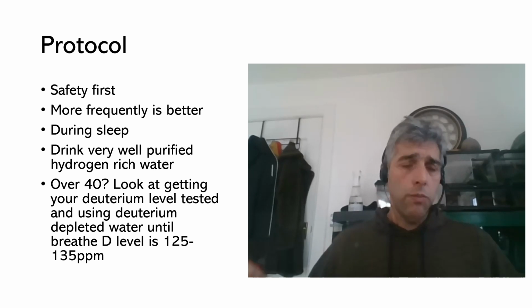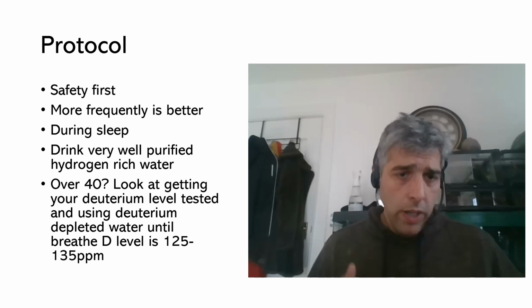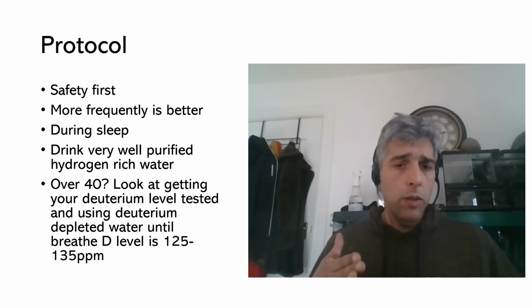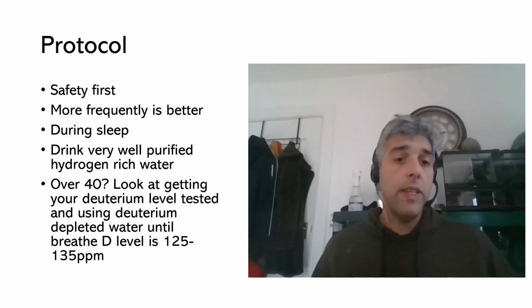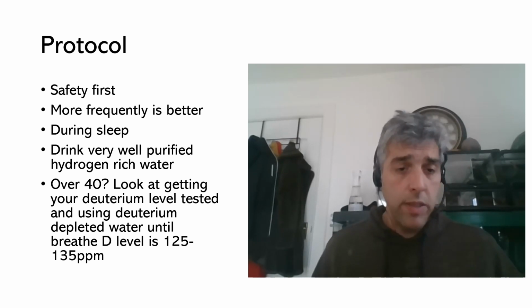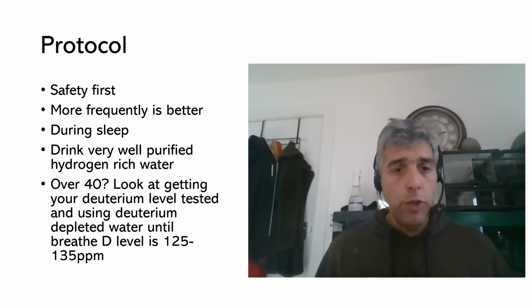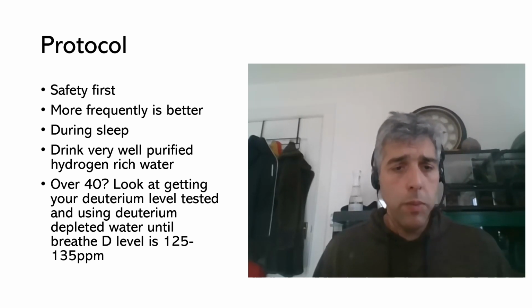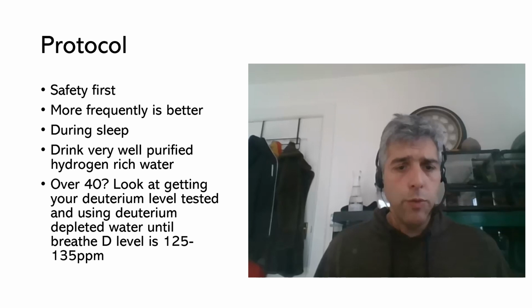Just like a car needs to be safe to be on the road. Any hydrogen-generating machine will need pressure switches and stuff in it. These are parts that fail and need testing, and they might not necessarily have redundancy built into them. So it's really important that whichever machine you choose, you get it from a source where they are doing proper safety, maintenance and testing. And that's really all I need to say in this presentation.